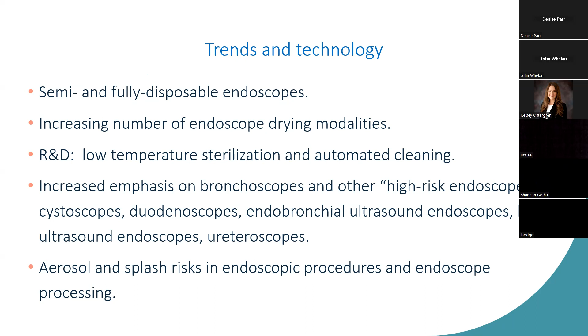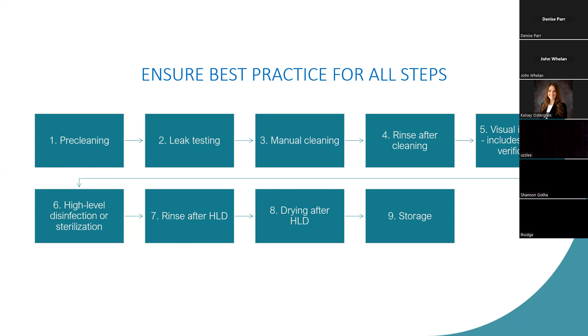So I want to finish by looking again at this very oversimplified list for the steps of processing. When it comes to processing of reusable devices, proactive quality control involves doubling down on the best practices for each step in the processes. So if we aren't leak testing each time, we risk contamination for the scope, ineffective high-level disinfection or sterilization, infection risk for the patients that follow. If we're not completely cleaning, we again limit the success for HLD or sterilization. If we don't take the time for inspection, we miss the chance to catch damage or bioburden that would inhibit effective processing. And so that's purposely where we need to double down and double check and not assume.